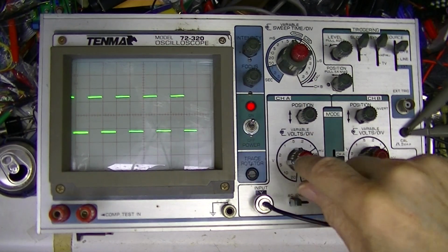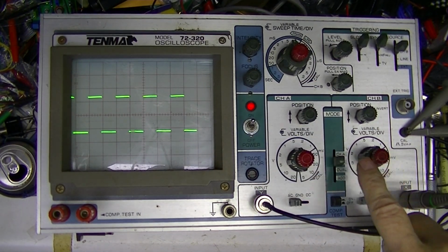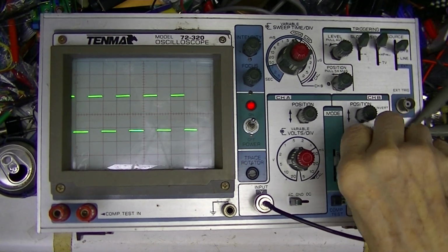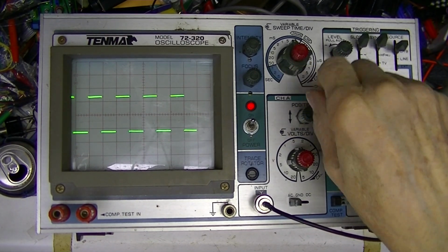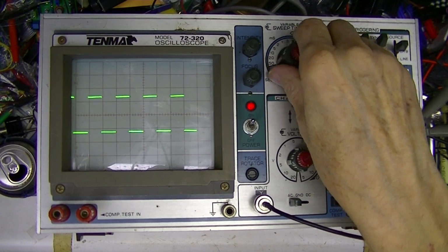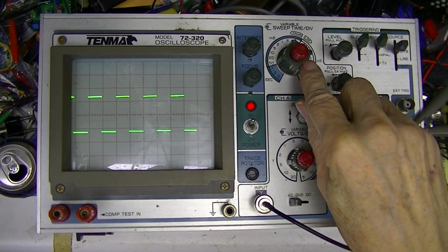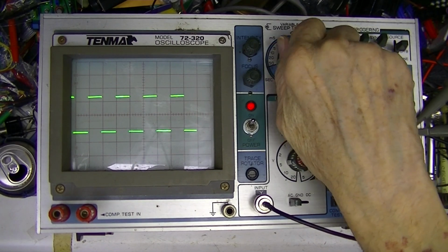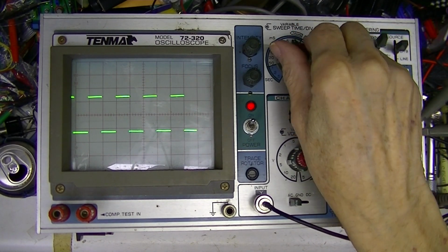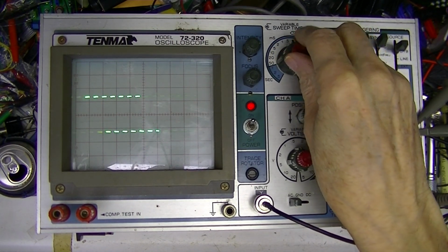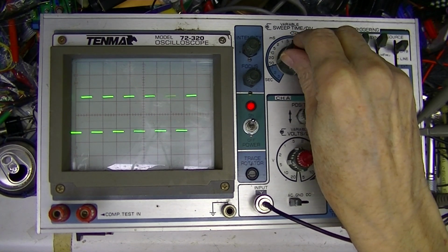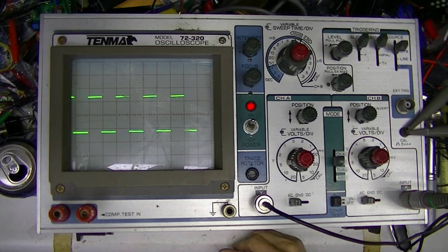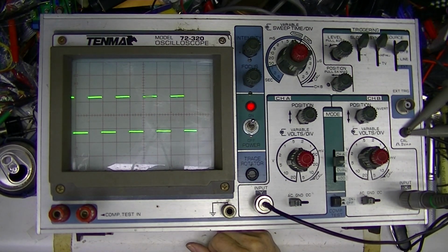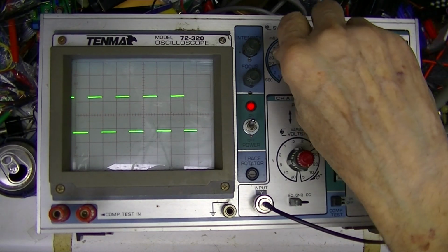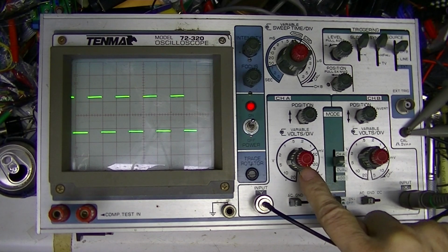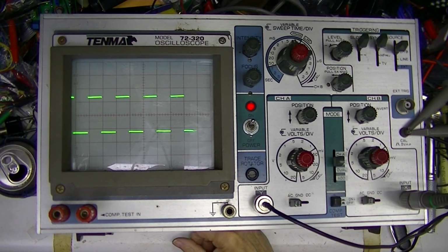So in addition to measuring voltage using this, I'm running the channel B, using this scale, I can measure time, repetition, using this scale. Again, it's only calibrated when the red knob is in this clockwise position. And you'll notice there's an arrow that says calibrate. So we don't know what the repetition rate is now, but there are times when we want to adjust the repetition rate to provide the signal somewhere in this viewing area. If these red knobs are all completely clockwise, these dials are accurate, or as accurate as the scope is.